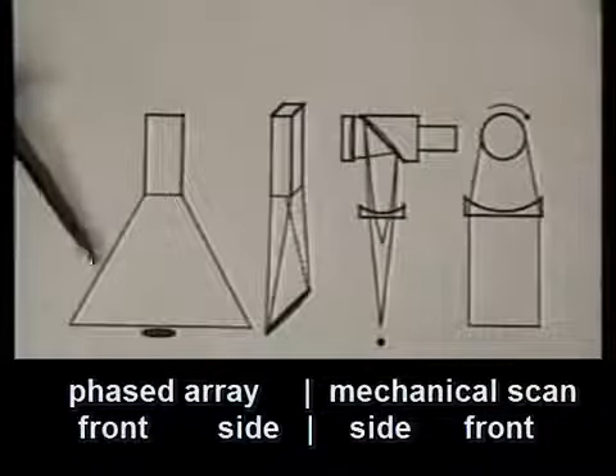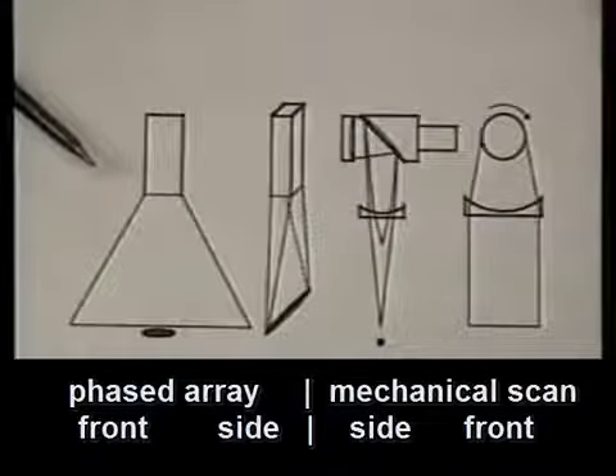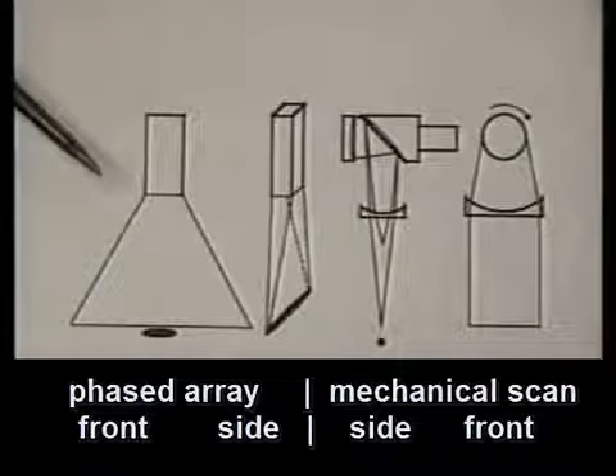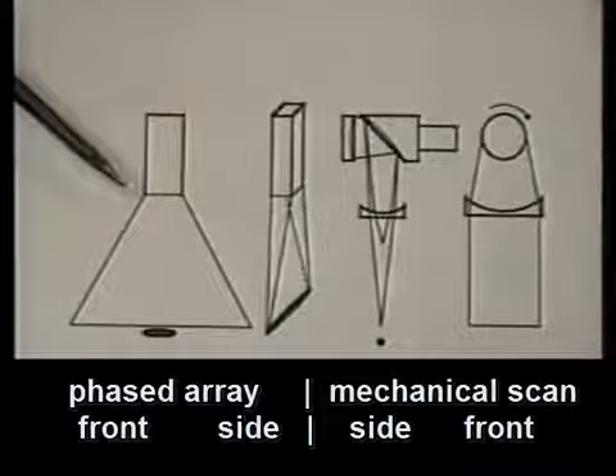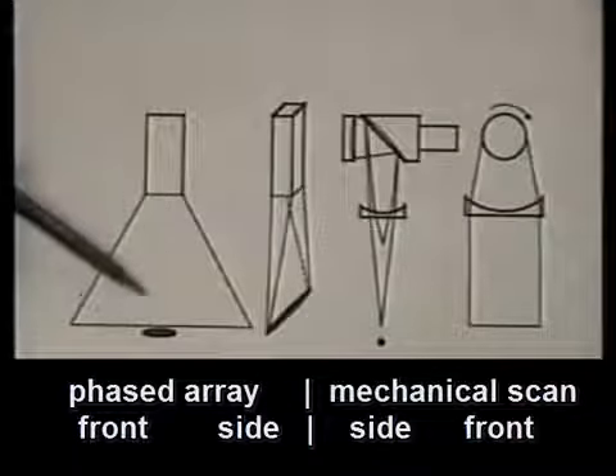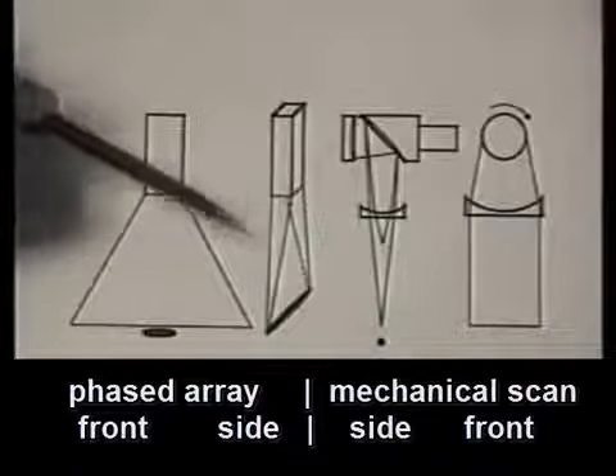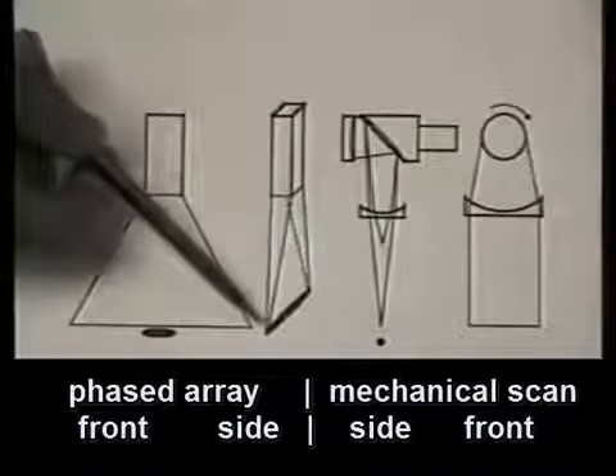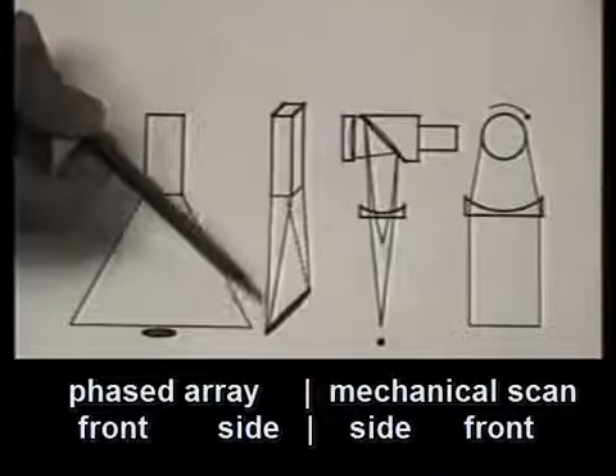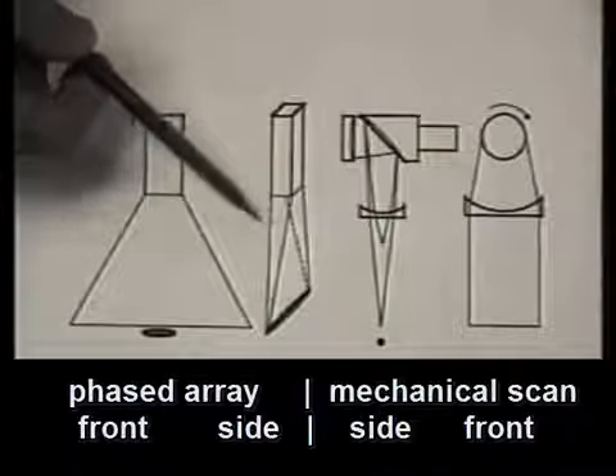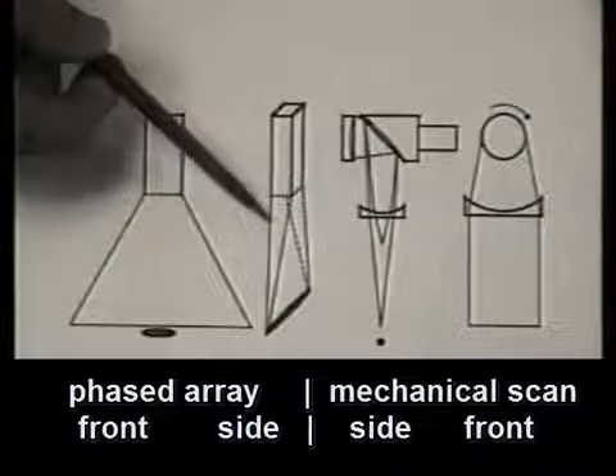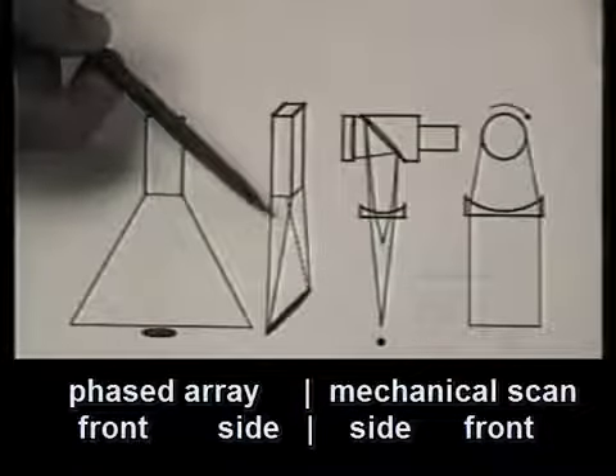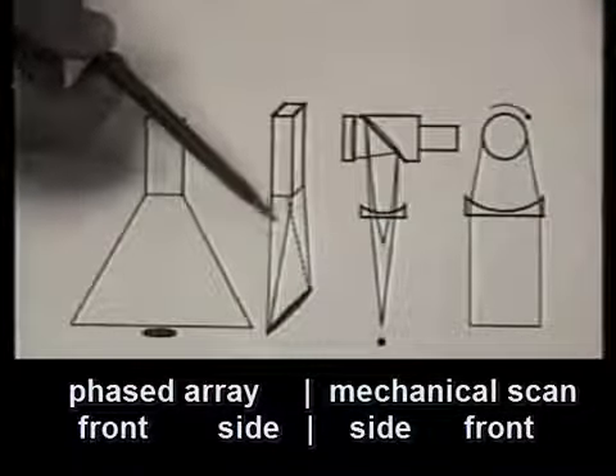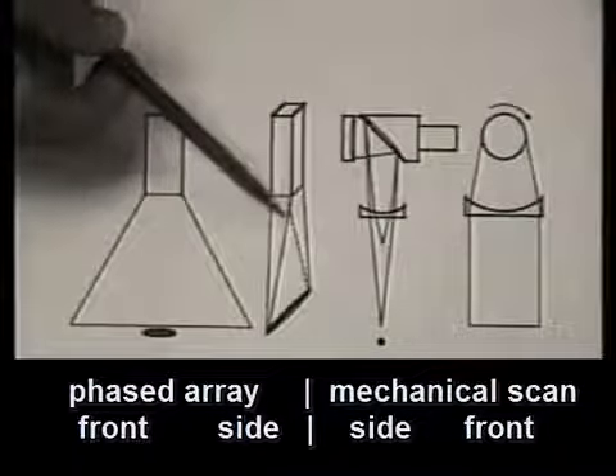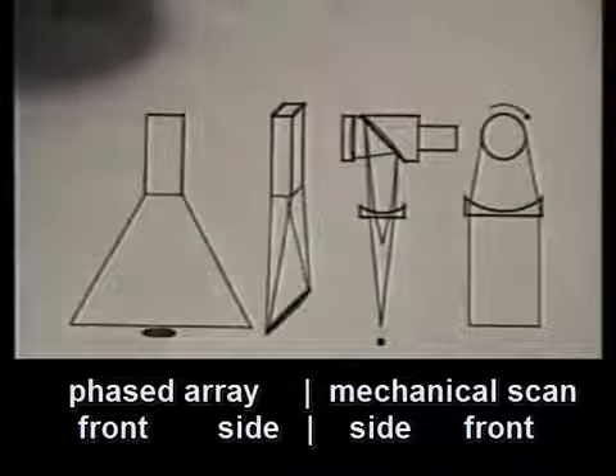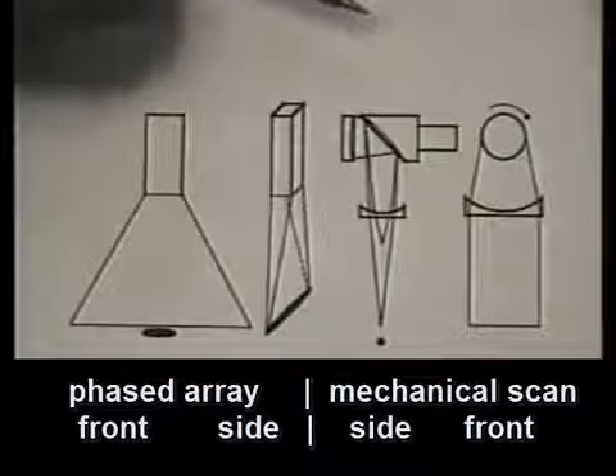Phased arrays produce a pie-shaped scan, which must first be scan converted to be displayed on a computer screen, which has a rectilinear display. They cannot achieve good resolution near the skin, and the useful information is in the far 2/3 of the image range. Visualized at right angles to the scan, it is only narrow at its farther range, and is progressively coarser at shorter ranges. In theory, phased arrays could match the resolution of mechanical scanning in both dimensions at all ranges, but this would require an array of about 10,000 electrodes and an equal number of processing circuits.